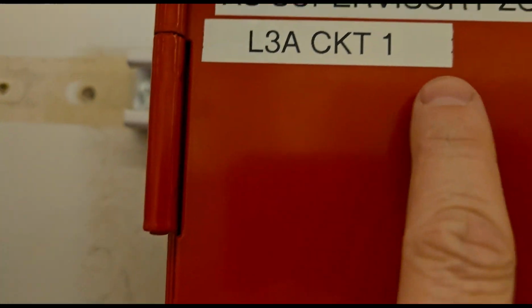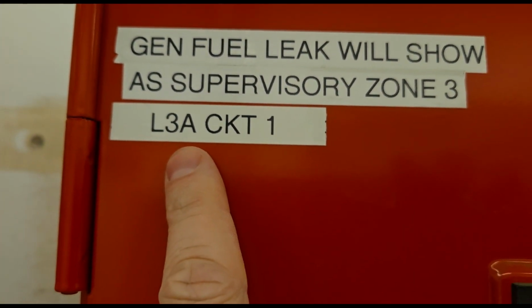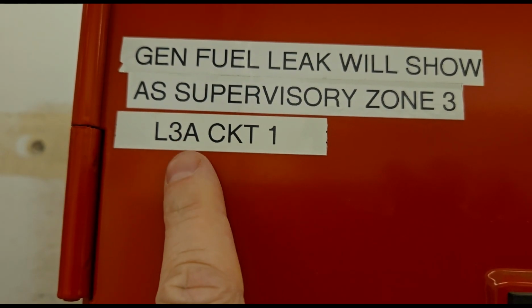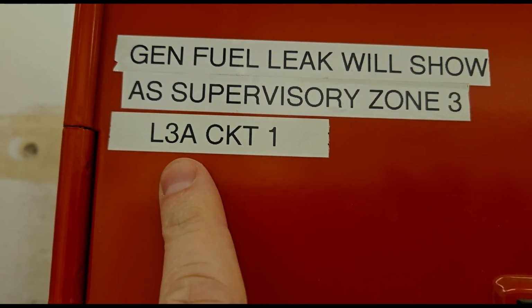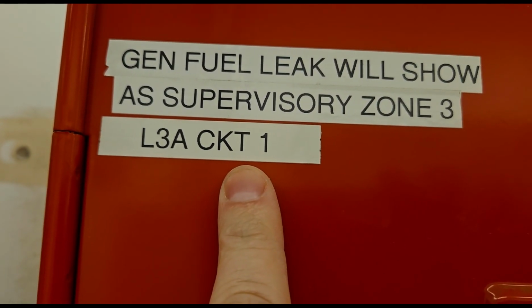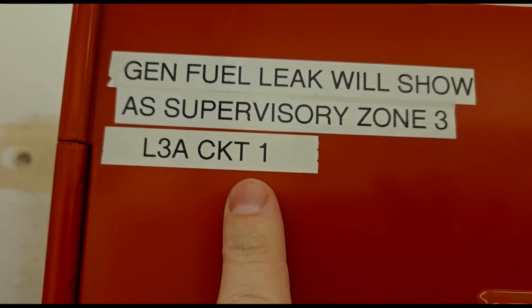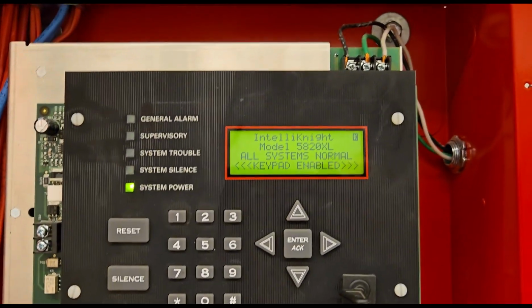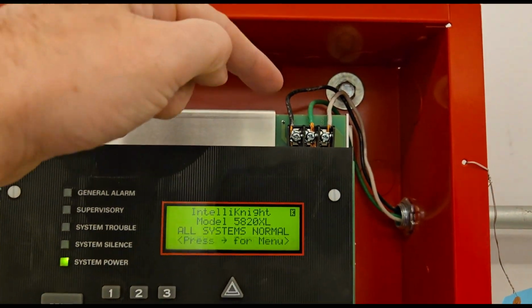So usually somewhere on the panel should be labeled the circuit breaker. Here it's located on the upper left. L3A is our circuit panel, and circuit number 1 is our specific breaker we're looking for. So L3A, circuit number 1. So before we do our disconnect test, we're going to identify where the power comes in, which is up here at the top.